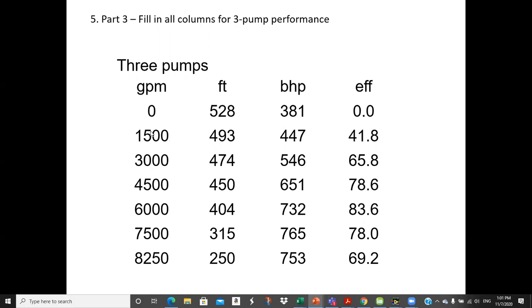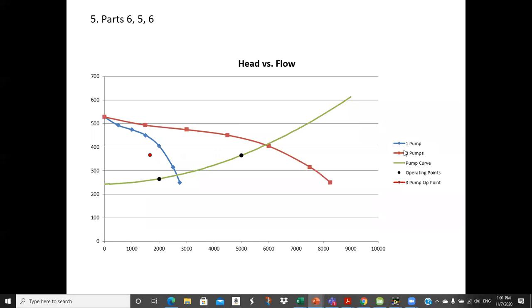This would be with 3 pumps operating. These are the operating points, and this is the brake horsepower. So you do the same thing. So that's pretty simple. And I'll show you the Excel sheet here in just a second. But this is the single curve. And so you take each one of these flows and you triple it, and then you plot the 3 pumps in parallel curve, and then you put your system curve on it.